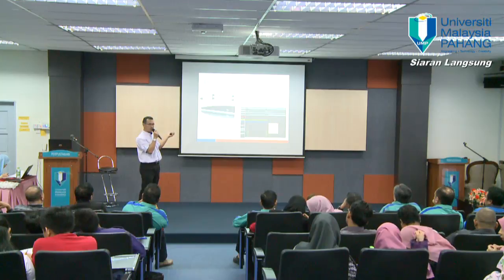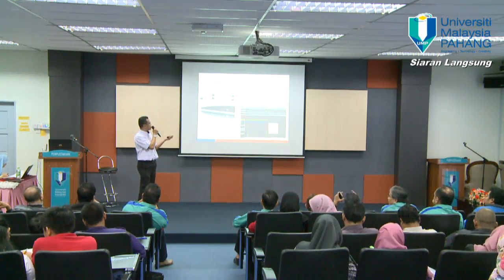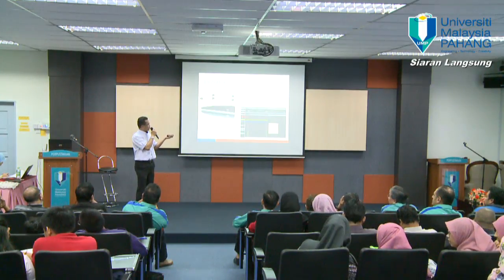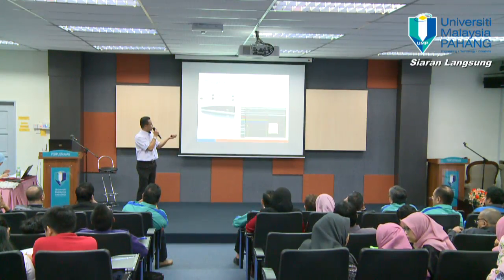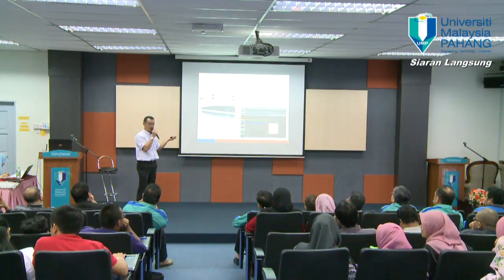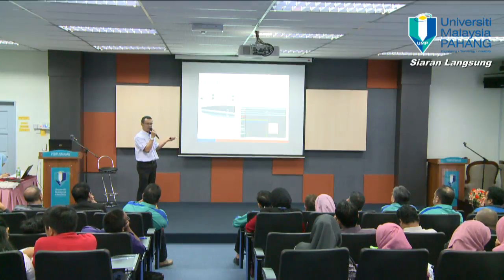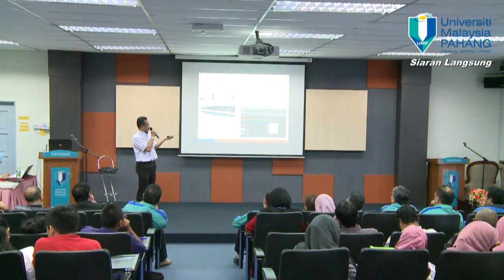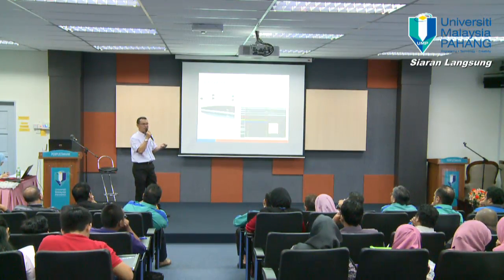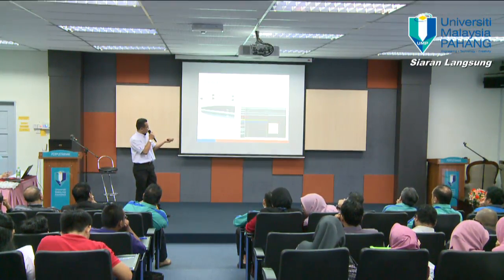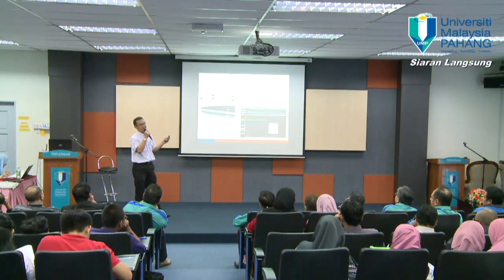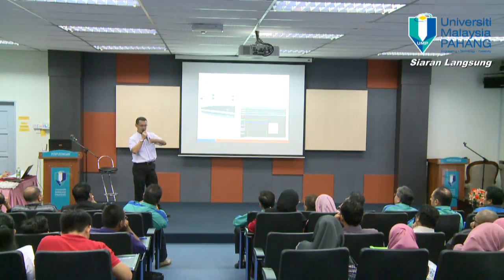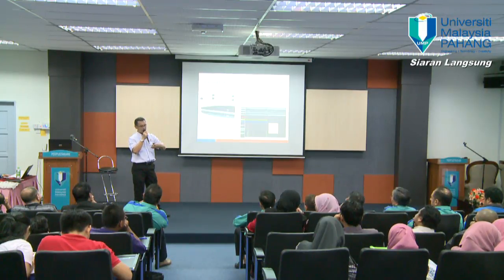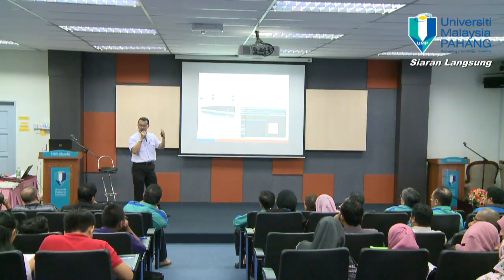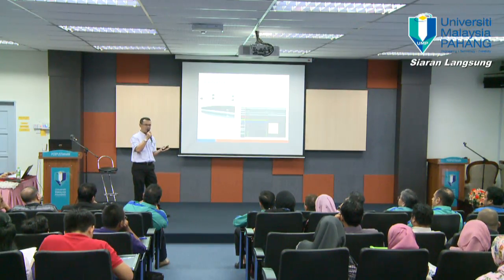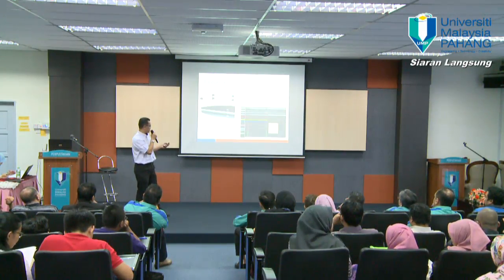Okay, at the PMU also we have a disturbance recorder. Disturbance recorder is normally we use to record all the disturbance. When the fault occur at the transmission line, even at the transformer, they will record the current and the voltage distortion here. It's the good of the disturbance recorder ni, they can tell us where the fault. It can calculate and tell us where the fault, and let's say from Mac City to Kuantan PMU, kalau you bawa perasan dekat Kuantan Batu Empat tu ada sebelah kiri tu, they can exactly where the fault occur, and then we know apa itu kerosakan yang jenis macam mana, ada pokok ke, konduktor putus ke, they can tell us exactly.